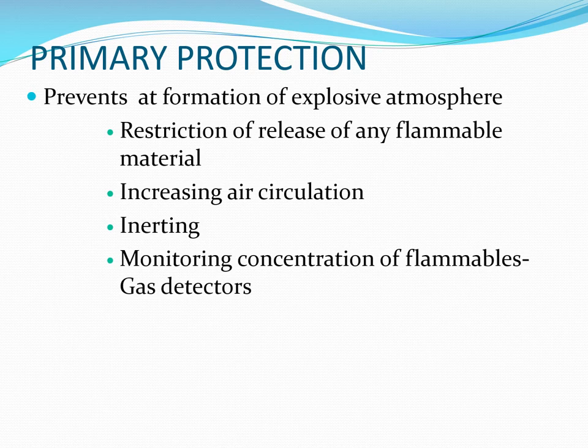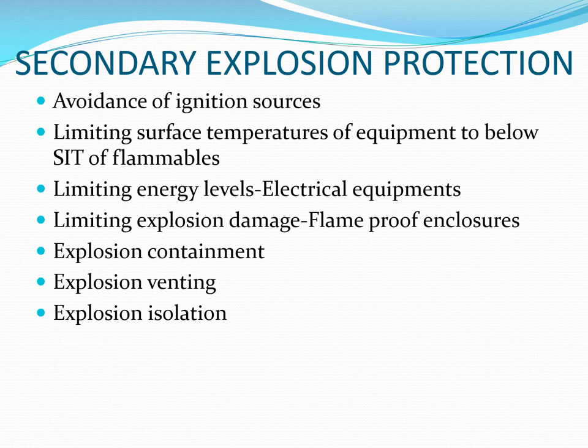Primary explosion protection aims at preventing the formation of an explosive atmosphere. This can be achieved by avoiding or restricting the release of any flammable material, increasing air circulation by natural or artificial ventilation to keep flammable concentrations below the LFL (lower flammability limit), inerting by adding nitrogen or carbon dioxide, and monitoring concentrations of flammables through gas detection systems.